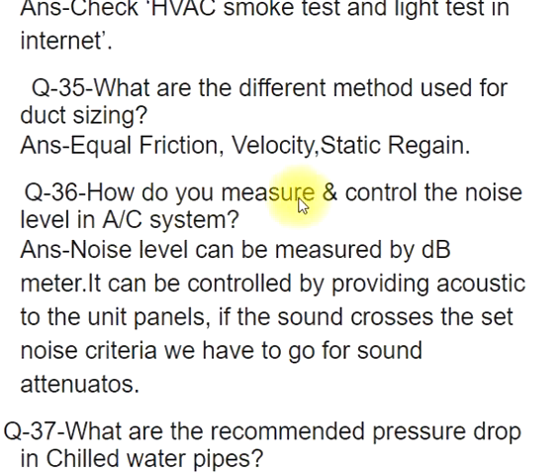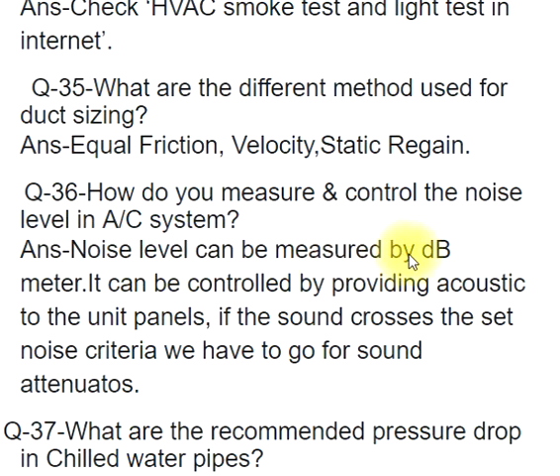Q36: How do you measure and control the noise level in an A/C system? ANS: Noise level can be measured by a dB meter. It can be controlled by providing acoustic treatment to unit panels. If sound crosses the set noise criteria, we have to go for sound attenuators.